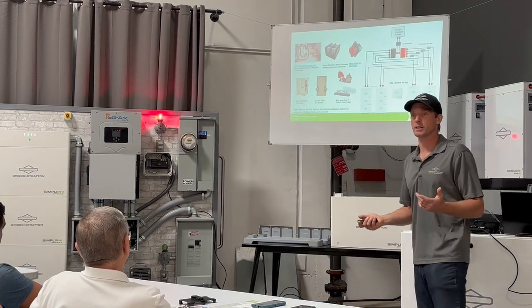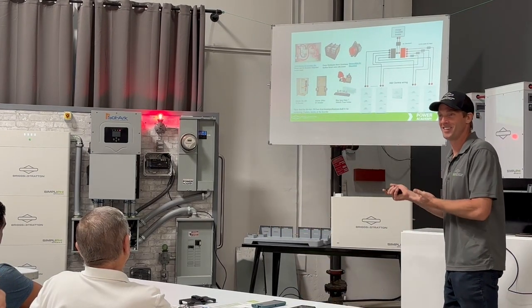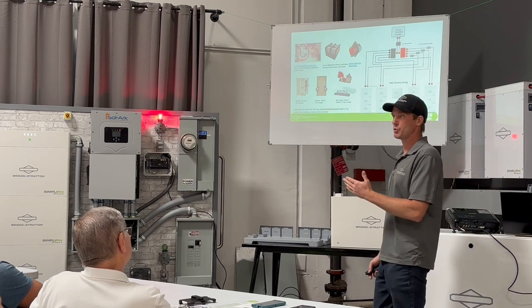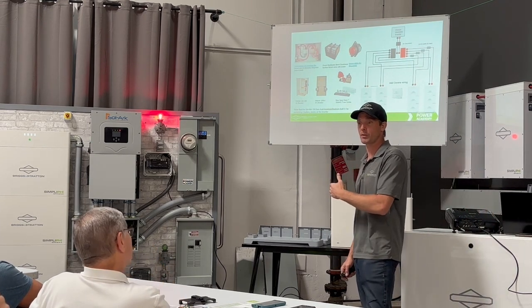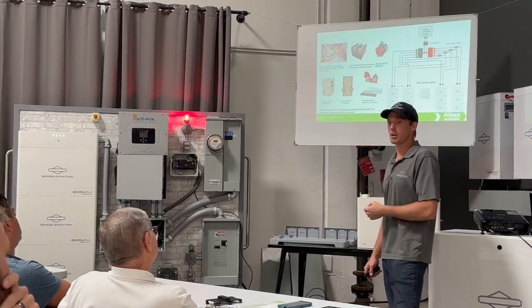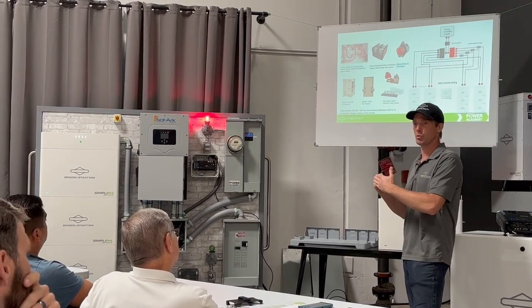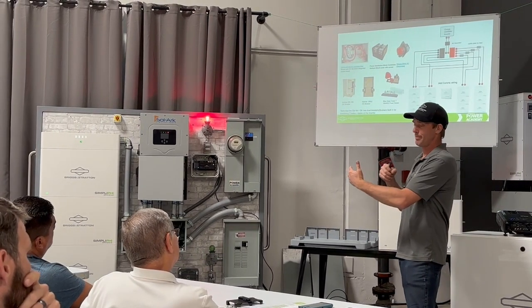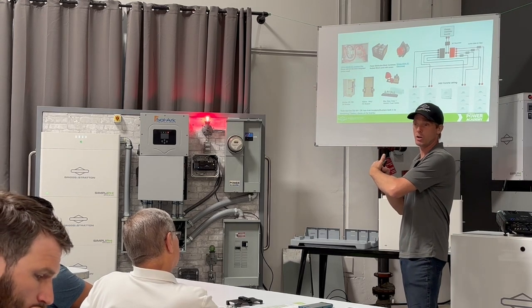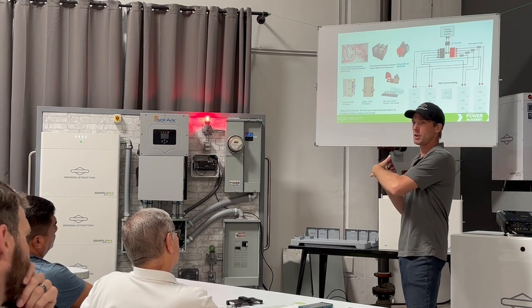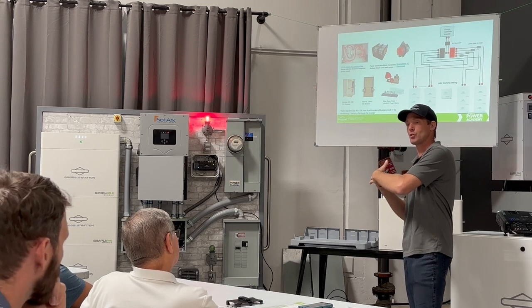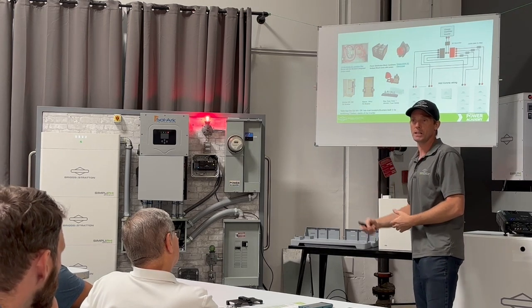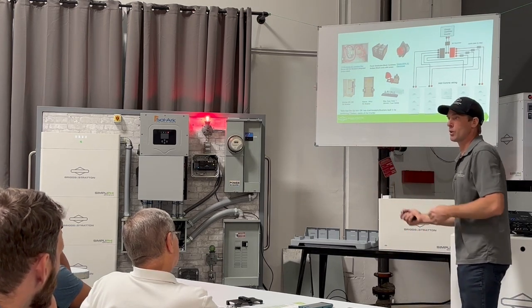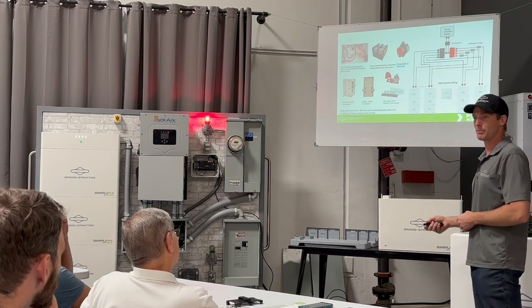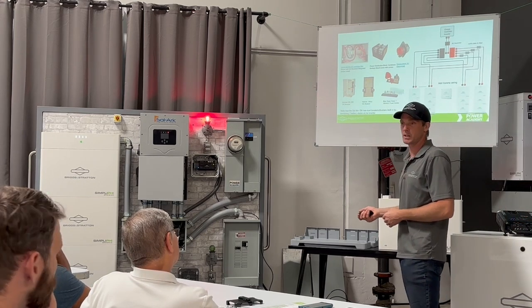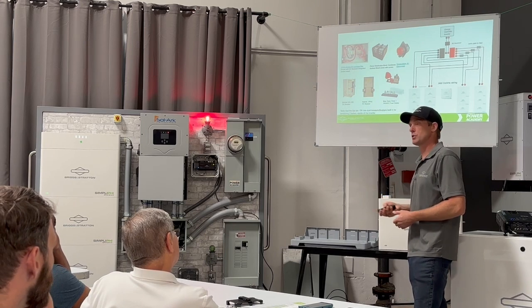Yes, it costs $100 as opposed to $16, but for safety reasons, if you buy one of those cheap switches off Amazon, it's going to heat up. There's contact resistance in switches—they work by bringing two surfaces in contact, and if there's not a lot of pressure, there's contact resistance. If you have resistance and lots of current flowing, you're generating heat inside the switch. I've seen people on forums complaining that their 500 amp switch using 100 amps keeps heating up and getting really hot. Well, it's because you bought a really cheap switch.